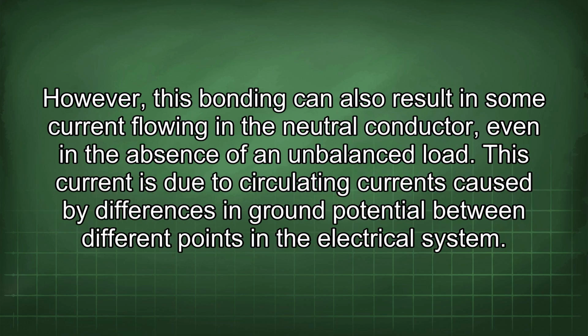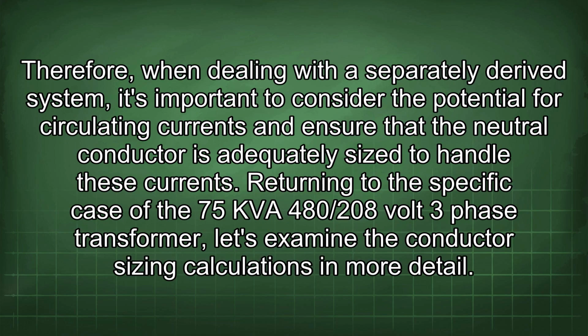However, this bonding can also result in some current flowing in the neutral conductor, even in the absence of an imbalanced load. This current is due to circulating currents caused by differences in ground potential between different points in the electrical system. Therefore, when dealing with a separately derived system, it's important to consider the potential for circulating currents and ensure that the neutral conductor is adequately sized to handle these currents.